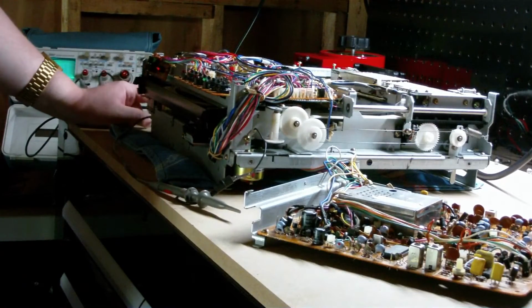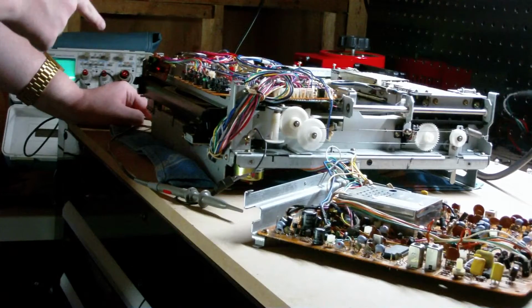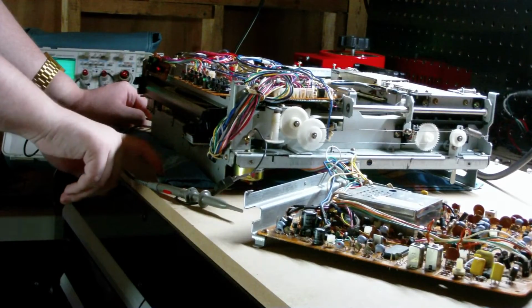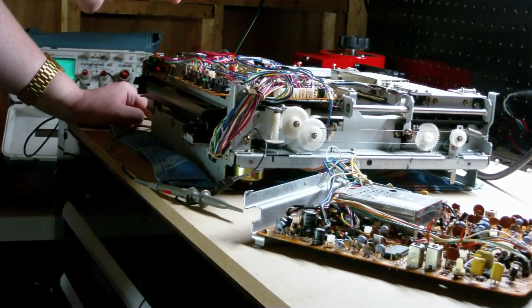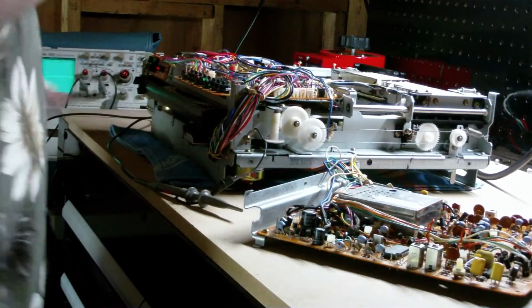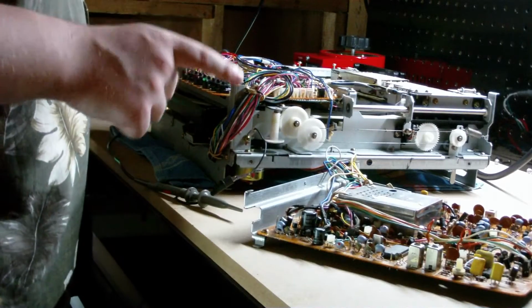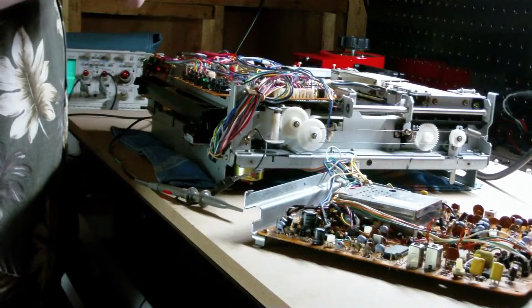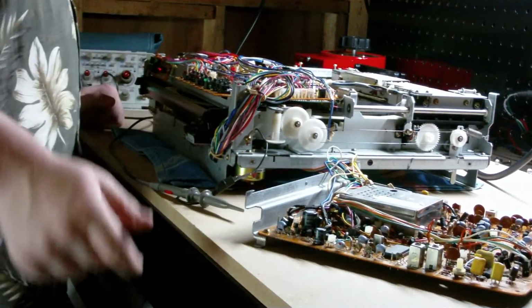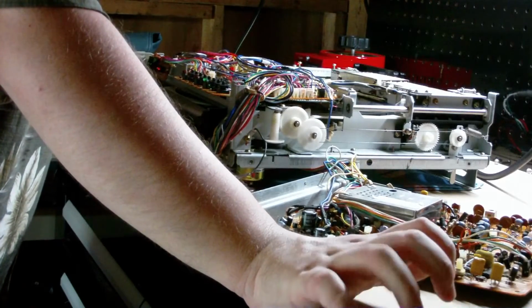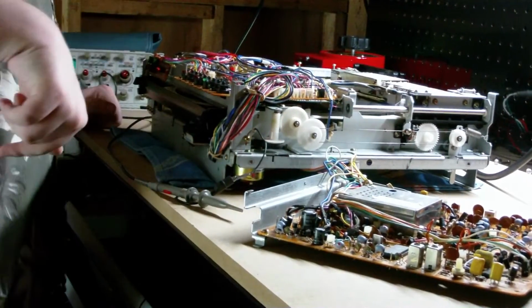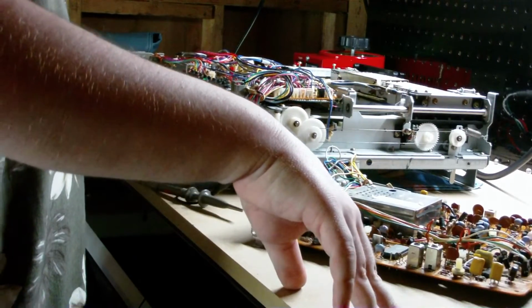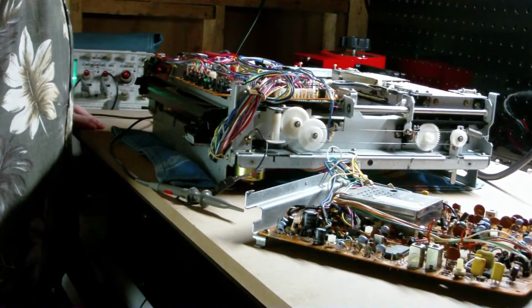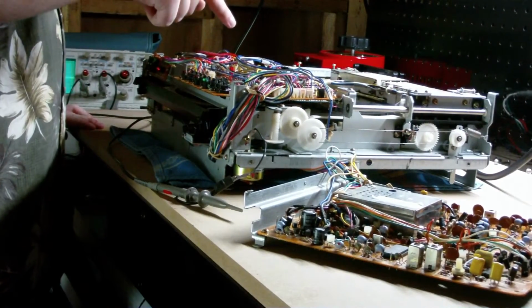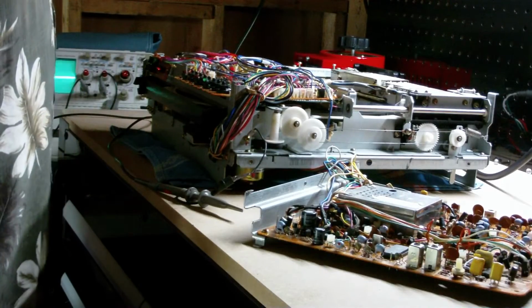So let's see. We have double dashes on the board. That means that either we're getting no DAXI off the disc or DAXI is heavily distorted. You can always put your scope on the appropriate test point. I'm blanking on where exactly the DAXI test point is on the system control here, but that is something you can do to see if there's anything there. I know in this case there's going to be no DAXI when I put the probe at the appropriate spot.